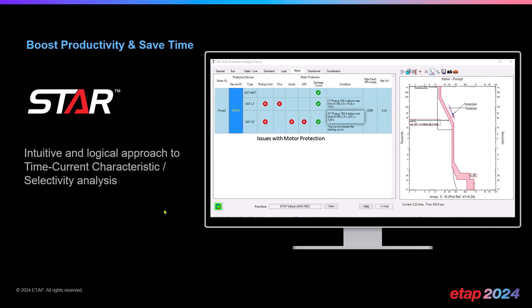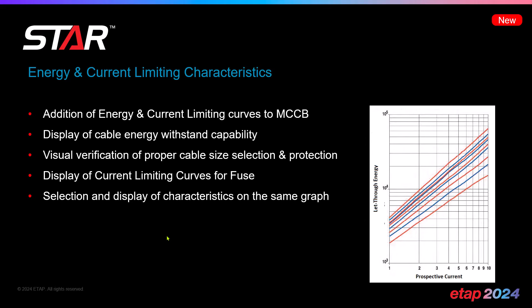Star, we have new capabilities. So for Star, what we have done is we've added the energy and current limiting curves for molded case circuit breakers, as well as the ability to display the current limiting curves for fuses. And once that is done, we are then able to do the following. We can auto-evaluate the cables now based on their let-through energy, and we can also evaluate the cable withstand versus the molded case circuit breaker let-through energy. And the verification of the permitted voltage drop can also be done based on a rule book that is established within Star. So this is a new characteristic view that allows you to visualize the let-through energy with respect to current and evaluate this with AutoStar along with your existing protection and coordination evaluation all in one shot.